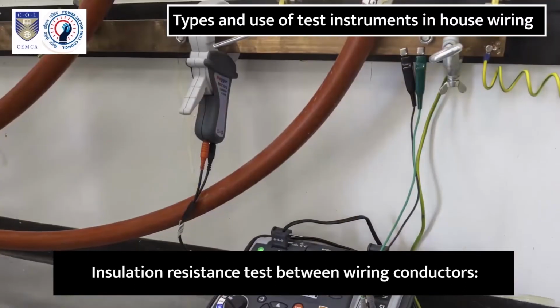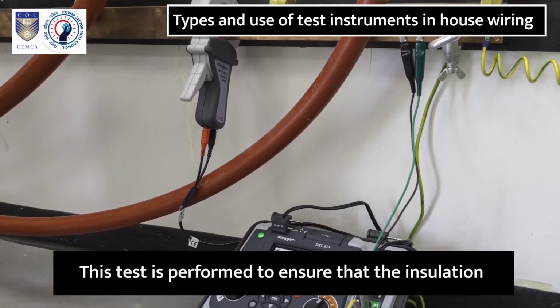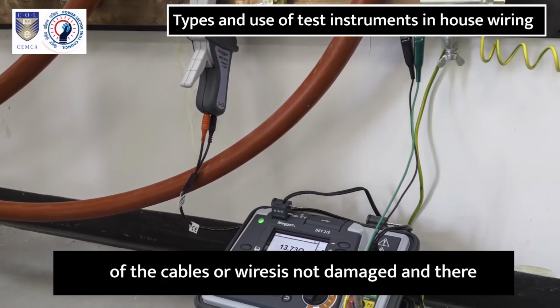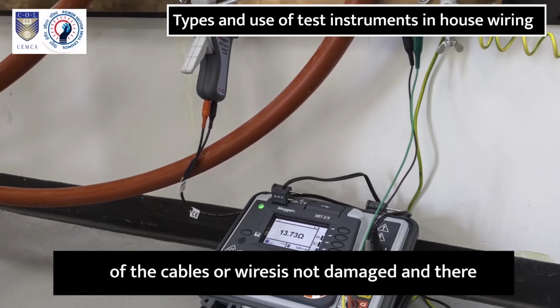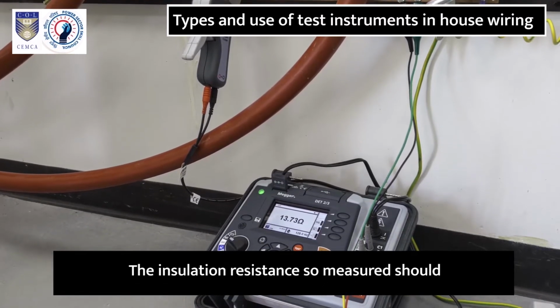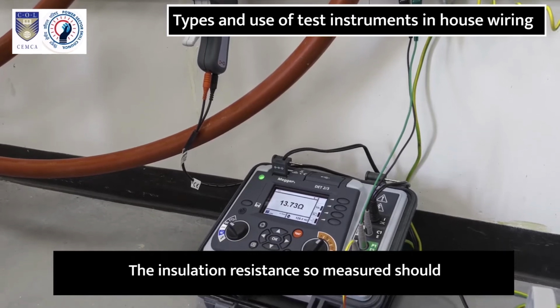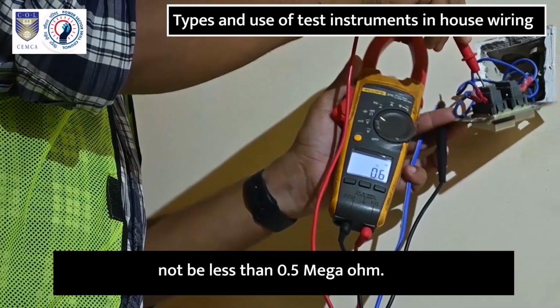Insulation resistance test between wiring conductors. This test is performed to ensure that the insulation of the cables or wires is not damaged and there is no leakage between them. The insulation resistance so measured should not be less than 0.5 mega ohm.